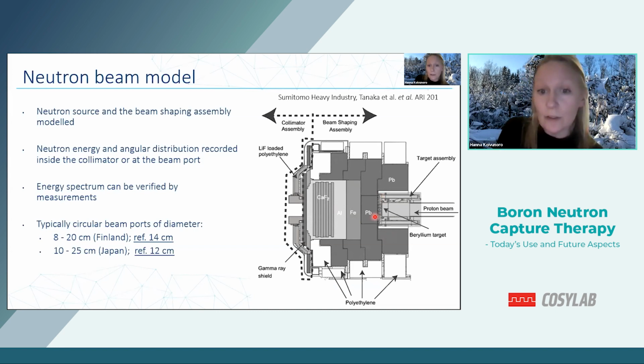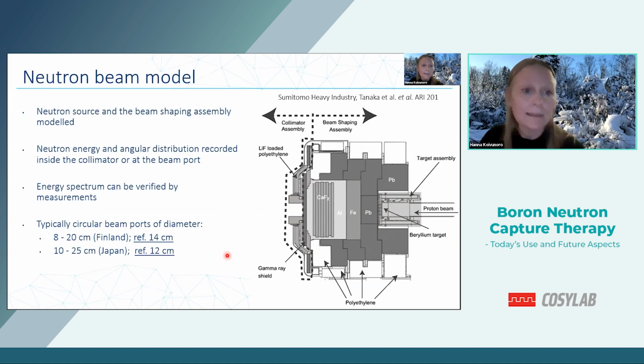So here is the neutron source. When the proton beam hits the target, that produces the neutrons, then there is the beam shaping assembly that slows down the neutrons to the epithermal region, and here is the beam port, and the patient is placed here. Typically, circular beam ports are applied in BNCT, from 8 to 10 centimeters diameter minimum up to 20 to 25 centimeters in diameter. Reference size in Finland is 14 centimeters and in Japan 12 centimeters.